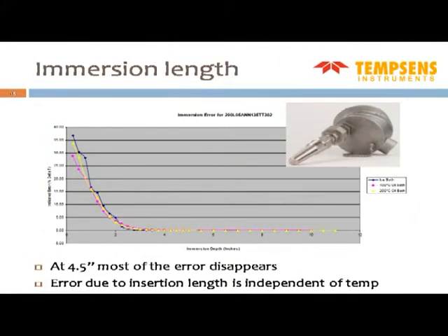For example, we have here a sensor at different temperatures. The blue one we can see is for ice at 0 degrees centigrade. Then the pink one is at 100, and the yellow one is at 200. We have done it in a calibration bath, and you can see the error. It is almost more than 4 inches for this dimension. 4 inches is about 115 to 120 mm. Beyond that we get the right kind of accuracy.